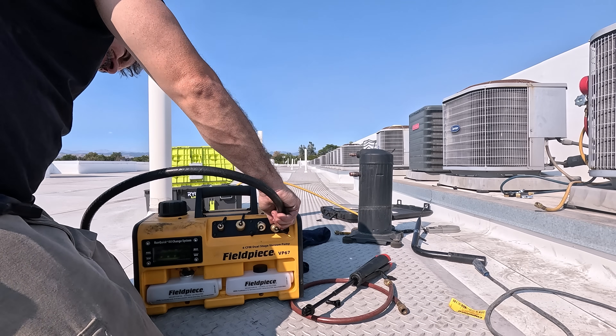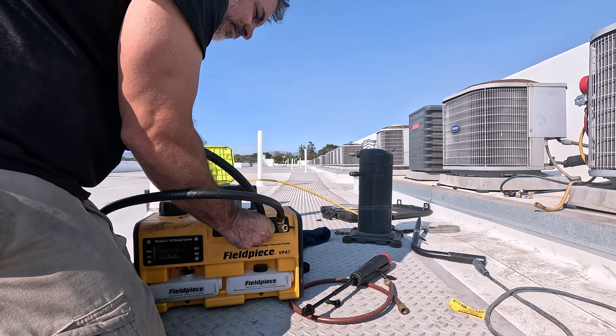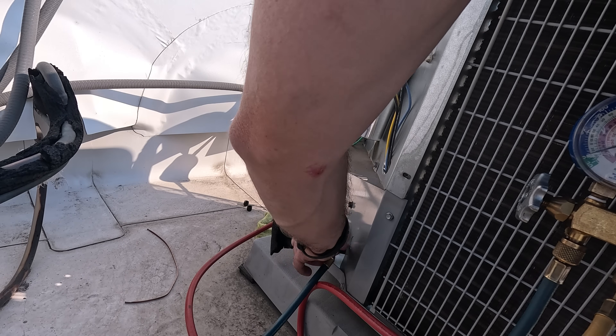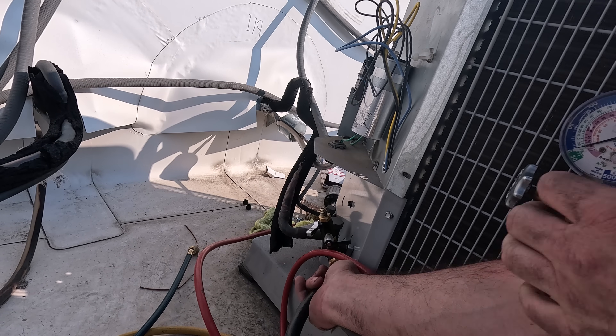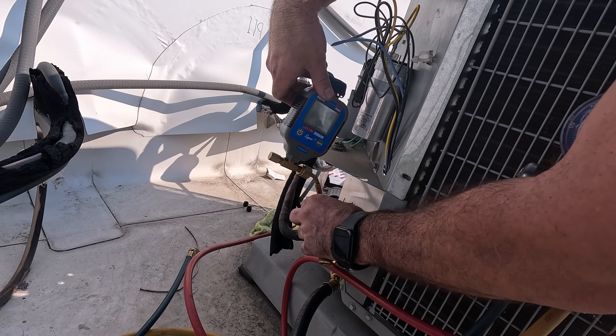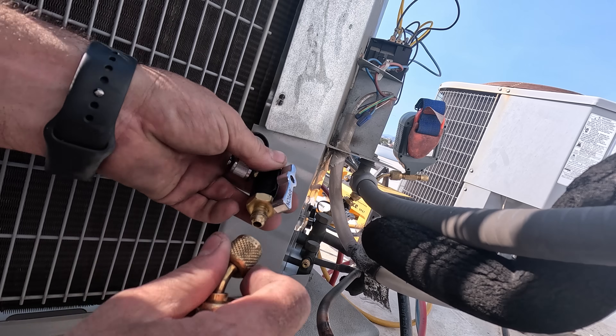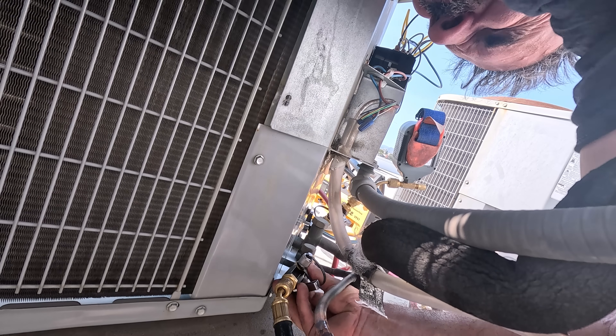For evacuation I'll be using the VP67 Field Piece vacuum pump with two 3/8 vacuum-rated hoses that I only use for vacuums. Both valve cores are already removed and I will keep those valve cores removed to speed up the evacuation process. I will be using three valve core removal tools made by Appion — they are vacuum rated. The reason I use three is so I can add an additional one for the micron gauge, so when it comes time to break vacuum I can easily isolate the gauge from the refrigerant.